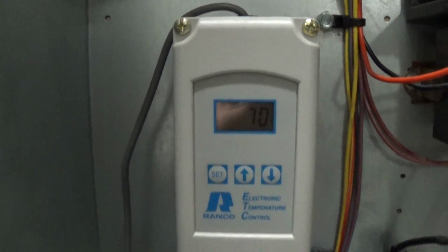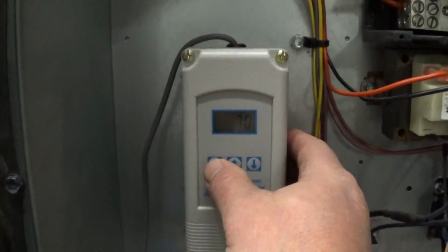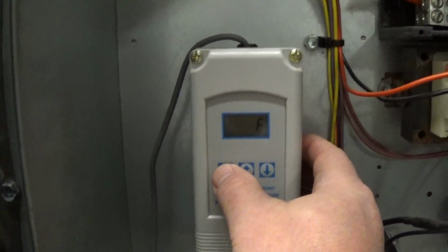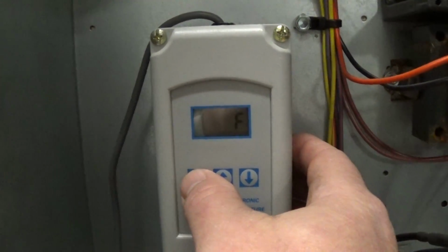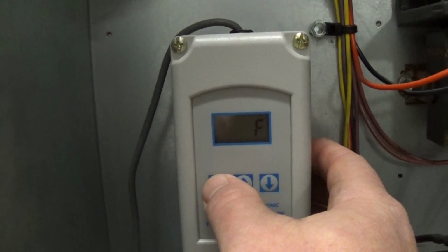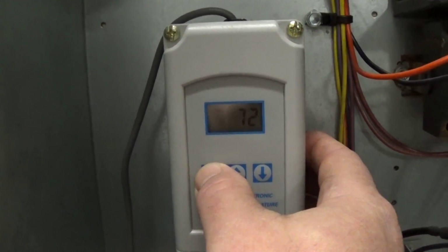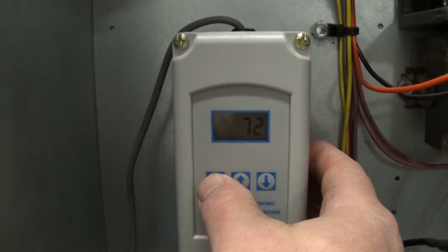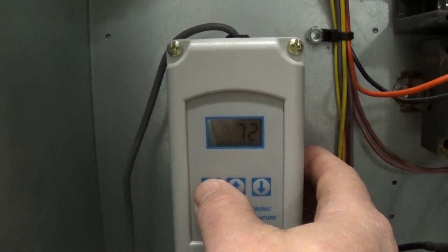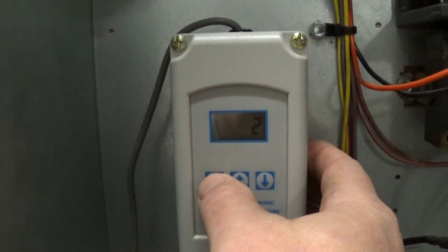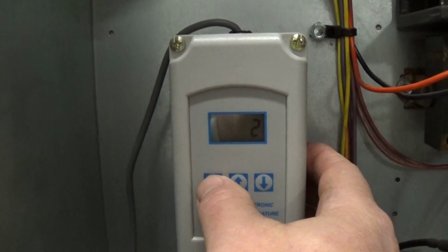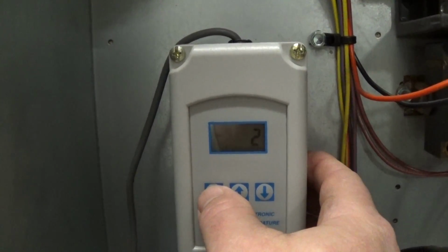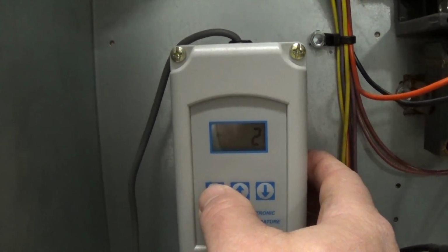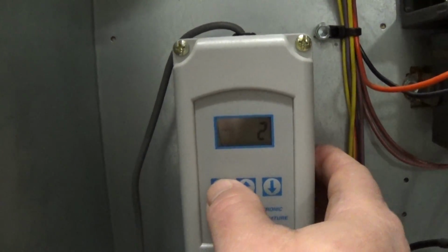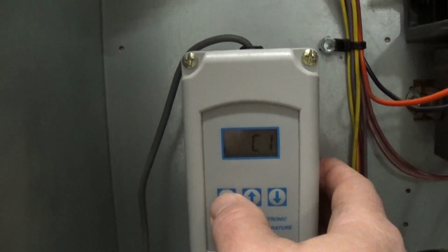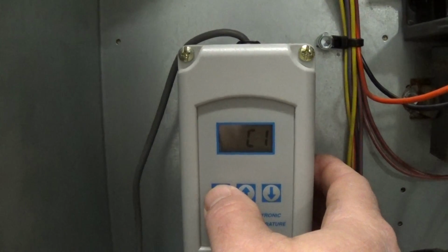in this case 70. You simply press set, and then we go into mode for cooling 1, or the compressor 1. We leave it at F for Fahrenheit. We press set again, and that gives us the set point for stage 1. Press set again, that gives us the differential. So it's going to go up 2 degrees or maybe higher until the compressor turns on again and cools it down to the set point. You press set again, and that's C1. You don't want an H1, you want to leave it in C1.